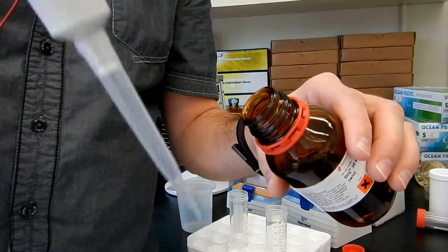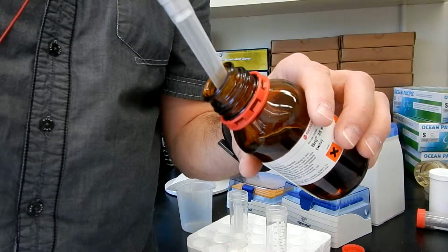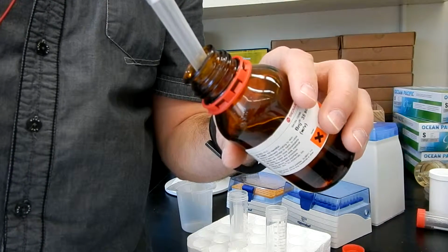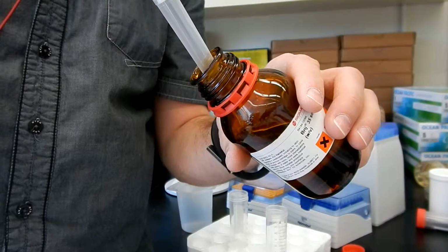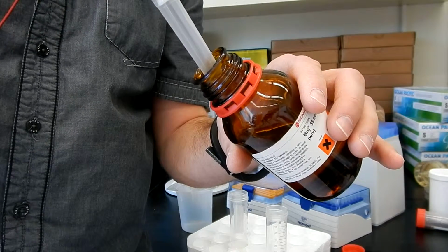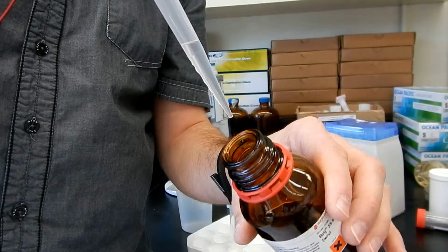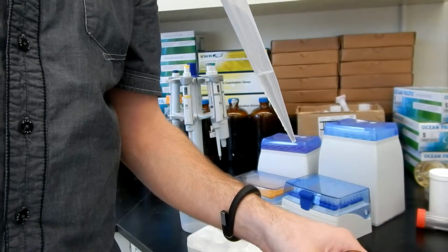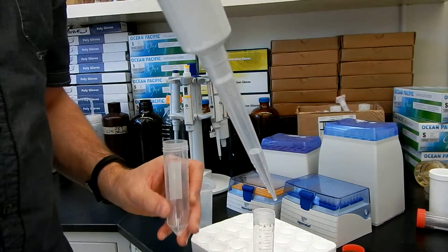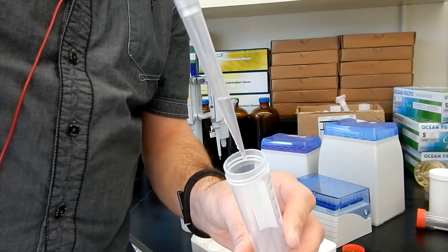Okay, so I press on the piston, go in the liquid, release slowly, and because the viscosity is higher, leave your tip a little bit longer so the pressure has time to equilibrate in the tip and this will give you the good volume. Otherwise, by the time the liquid gets in, if you go out too soon, then you won't have the good volume.